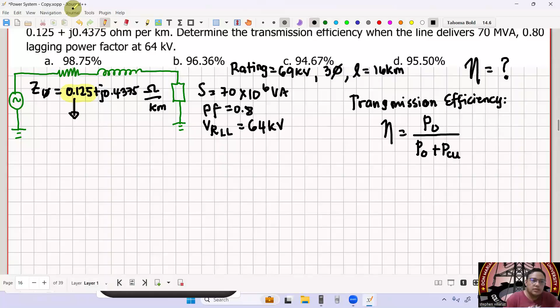Now how about the output power? Output power is just equal to, if we have S already, we take it from S. So that is S multiplied by the power factor. So efficiency is 70 mega times power factor 0.8, all over 70 times 10 raised to 6 times 0.8, plus our copper loss, PCU, which is equal to 3 times I per phase squared times R per phase.